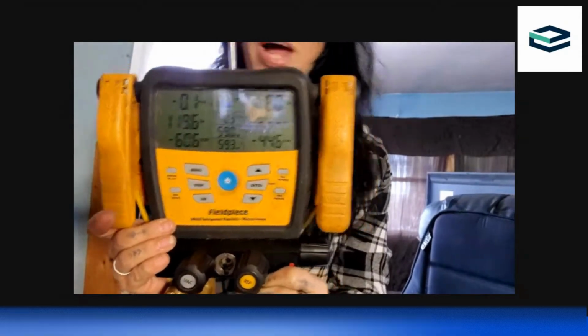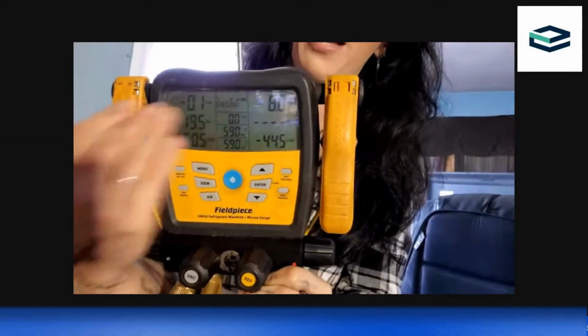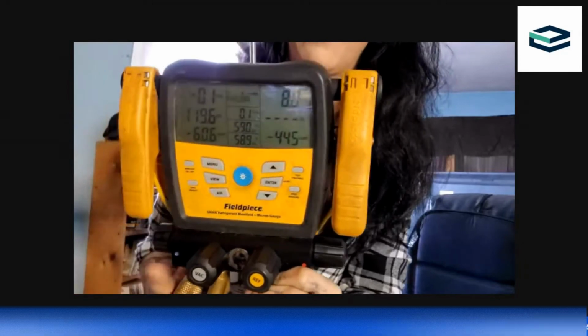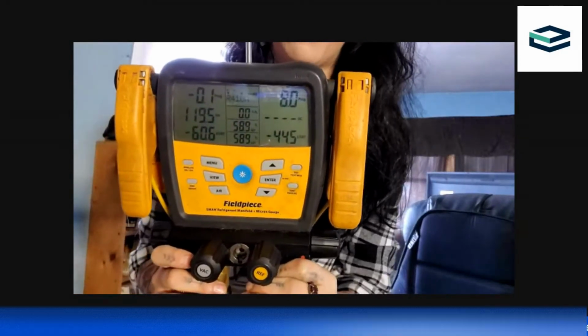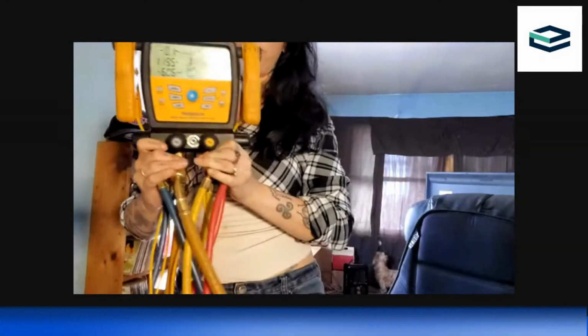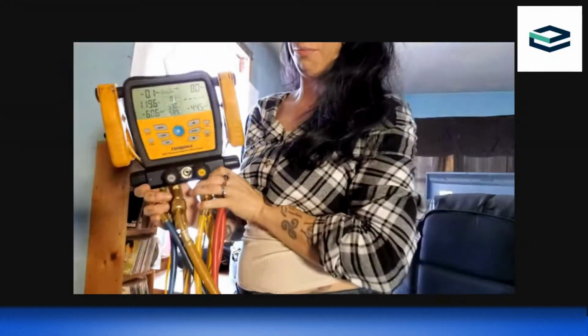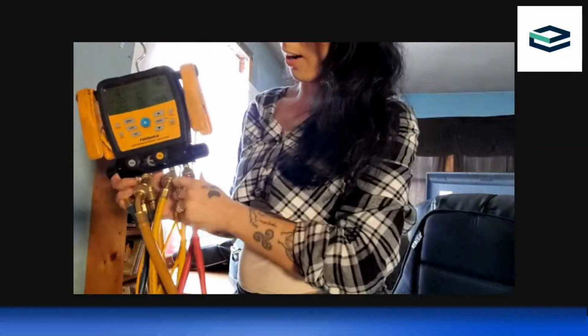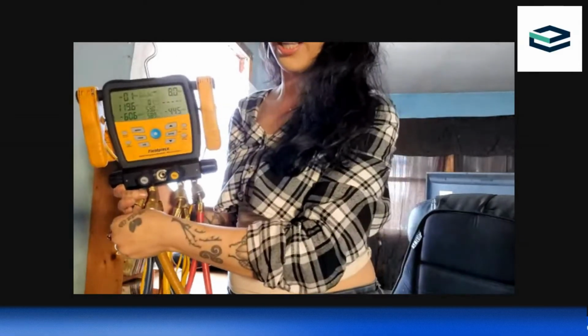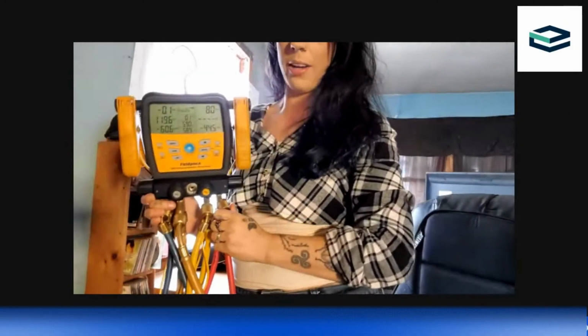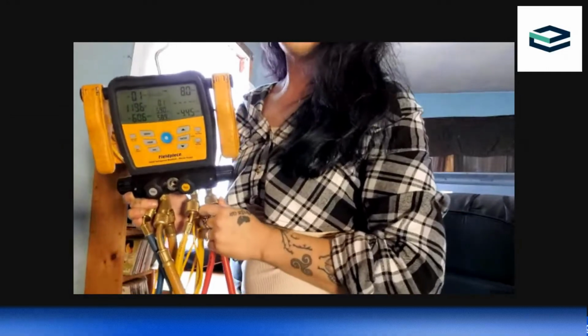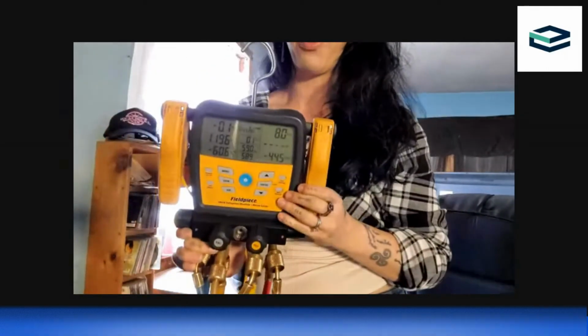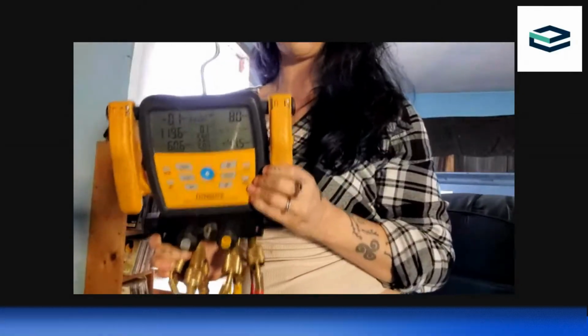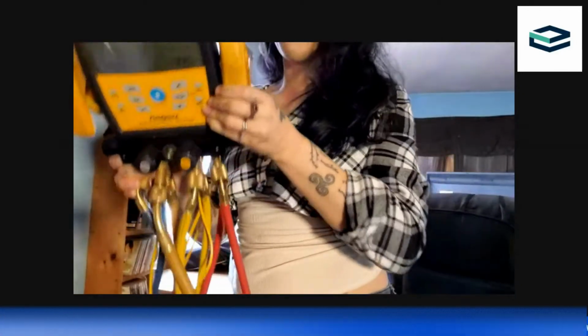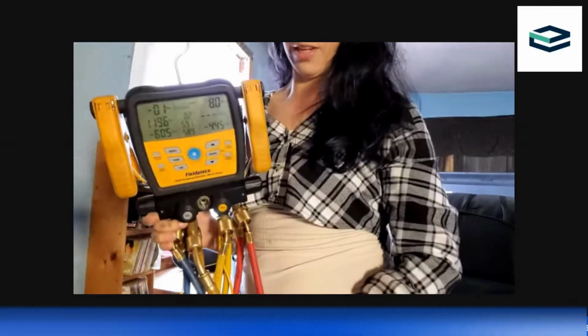This is what it will look like when you are hooked to a system. It will not have these temperatures or pressures, obviously. This is not hooked up, but this is what your gauge manifold will look like. This manifold is meant to tell you what's happening within the system by taking your high side and your low side, hooking them to those service ports that I showed you on the diagram, which I'll show you again. And then as you do that, it's able to cycle through. Because of this manifold, you become part of the refrigeration cycle. So the hoses are not the only important part of this.